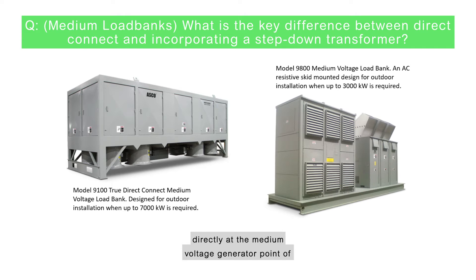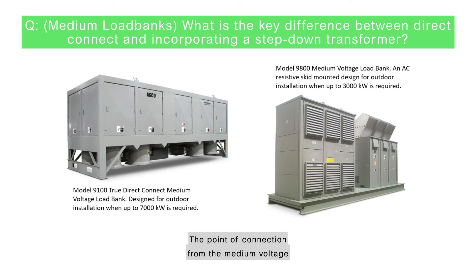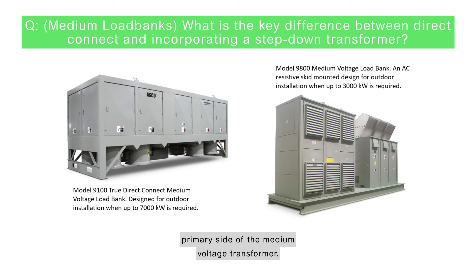With the model 9800 shown on the screen here, you are integrating a low voltage load bank, typically 480 volts, with a medium voltage transformer. The point of connection from the medium voltage generator to the load bank in this instance is the primary side of the medium voltage transformer.